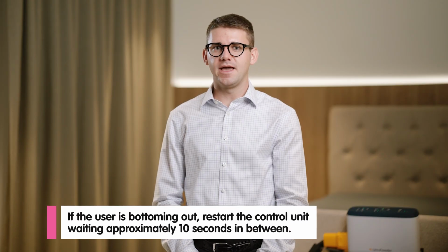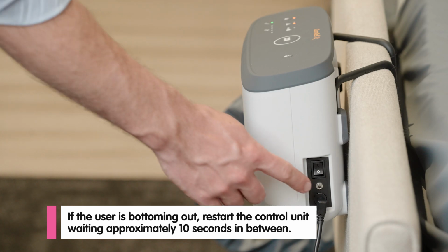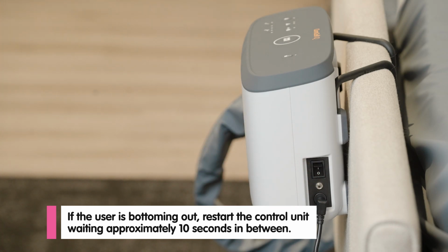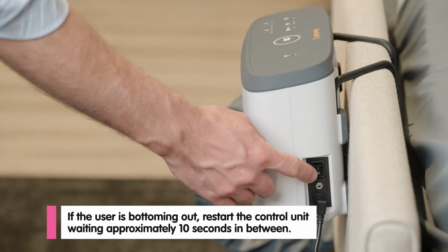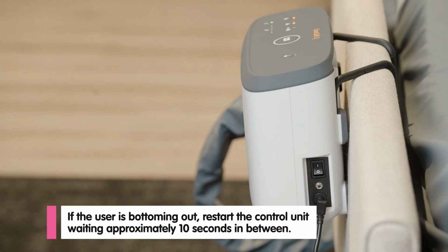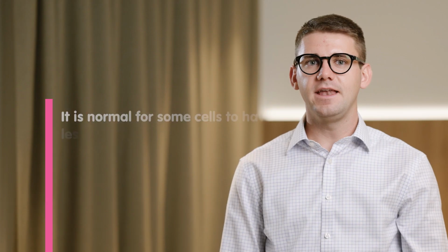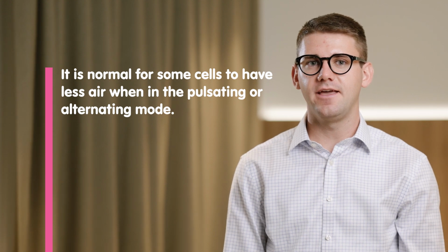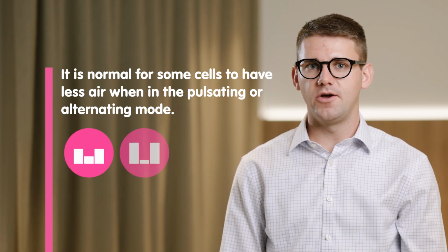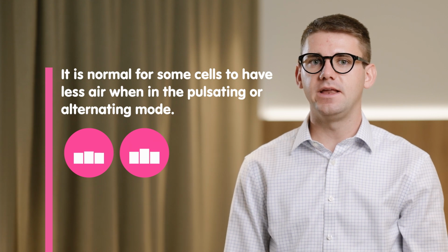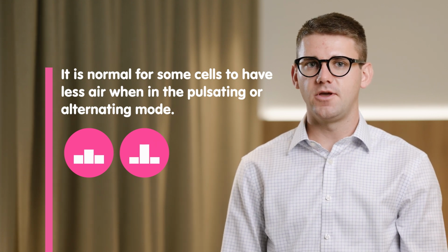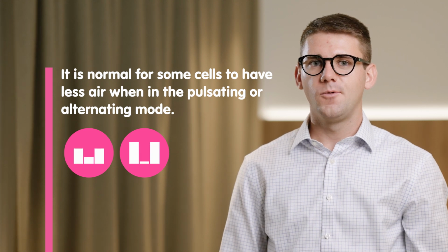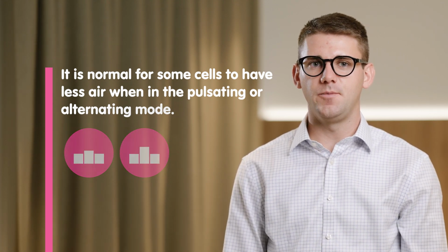If the user is bottoming out, restart the control unit by setting the on-off switch on the side of the control unit to the off position. Wait for approximately 10 seconds and restart the control unit. The control unit will initiate an automatic setting. Wait until the automatic setting is complete, then perform a hand check. It is normal for some cells to have less air when in the pulsating or alternating mode, as the air supply switches between alternating cells for a predetermined cycle period. Remember, one cycle equals 10 to 25 minutes.